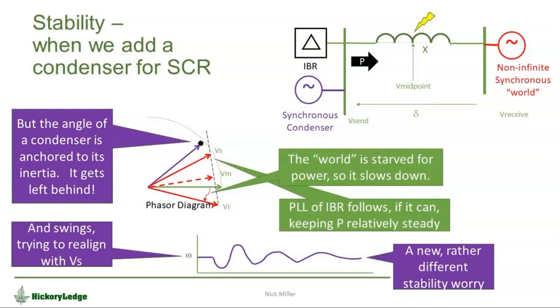It delivers current to keep the voltage healthy. It delivers system strength to help keep the inverter stable, but it gets left behind. And then, because it's relatively low inertia, with an inertia constant typically of one or so, it will get dragged because it has no prime mover and try to realign itself with the sending end VS of the inverter, and it bounces around. And if you don't get it right, that bouncing is unstable and the synchronous condenser rips off and you have a stability problem. And so we've gone possibly from out of the frying pan into the fire by the addition of the condenser.